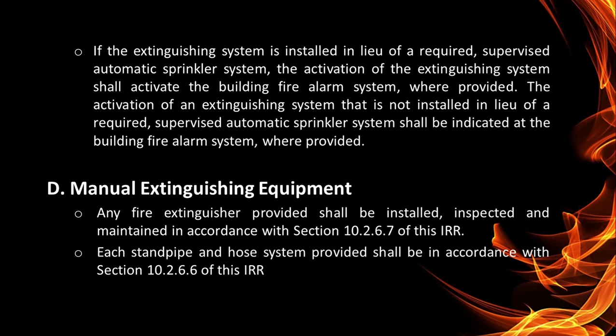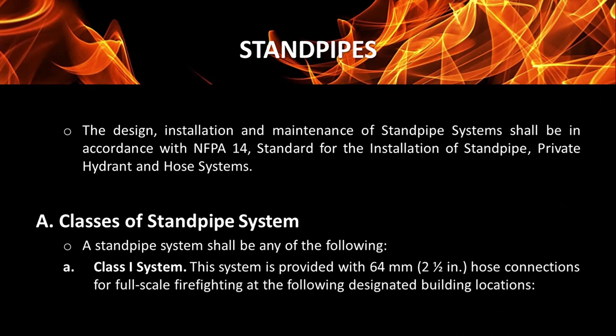Manual extinguishing equipment. Any fire extinguisher provided shall be installed, inspected, and maintained in accordance with Section 10.2.6.7 of this IRR. Each standpipe and hose system provided shall be in accordance with Section 10.2.6.6 of this IRR. Next is standpipes. The design, installation, and maintenance of standpipe systems shall be in accordance with NFPA 14, standard for the installation of standpipe, private hydrant, and hose systems.